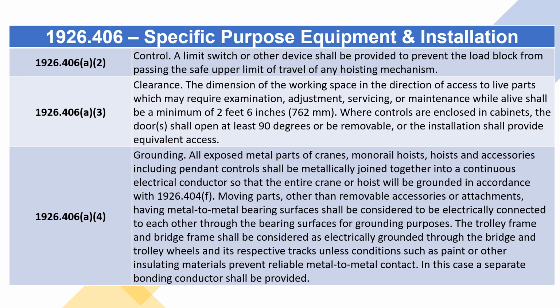1926.406(a)(3) Clearance. The dimension of the working space and the direction of access to live parts which may require examination, adjustment, servicing, or maintenance while alive shall be a minimum of 2 feet 6 inches, 762 millimeters. Where controls are enclosed in cabinets, the doors shall open at least 90 degrees or be removable, or the installation shall provide equivalent access.